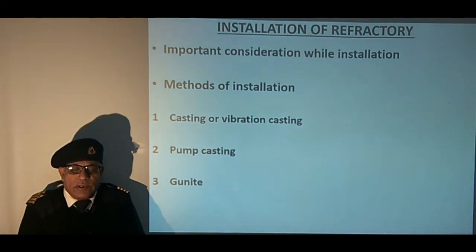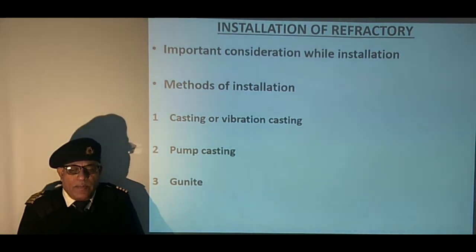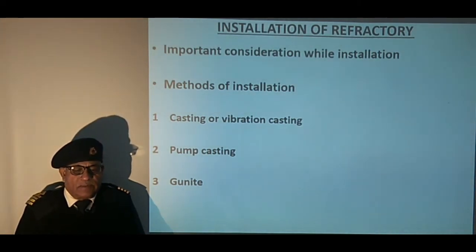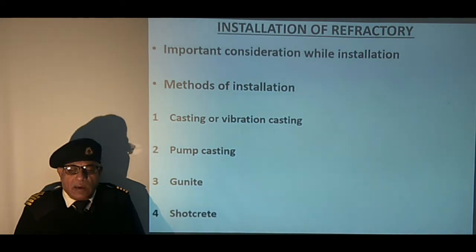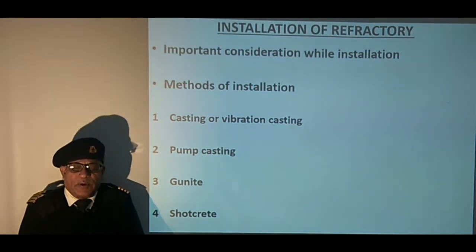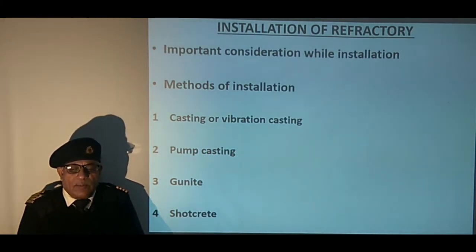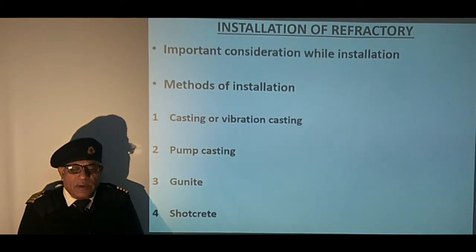Gunite is dry monolithic refractory applied with air-operated gun-like equipment; water or additives are introduced at the nozzle to moisten the dry refractory to stick on the surface. Shotcrete is typically a low cement, low moisture refractory which is fully tempered and mixed with water or special additives, then applied through a machine using a piston pump and air to spray wet material from the nozzle.